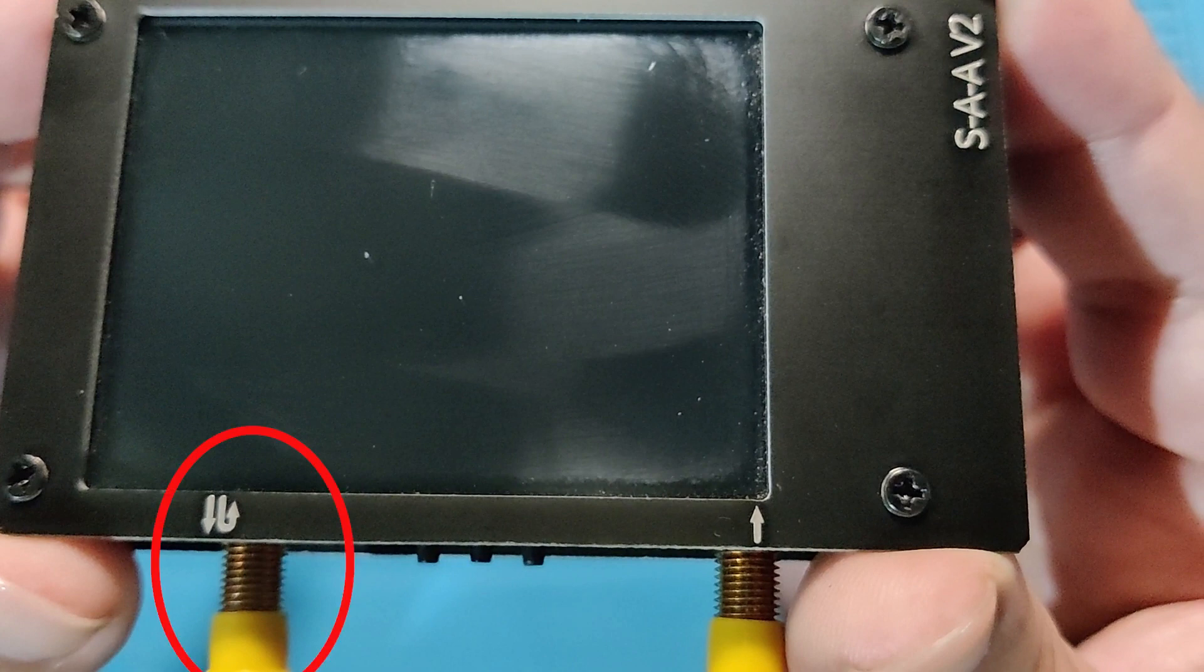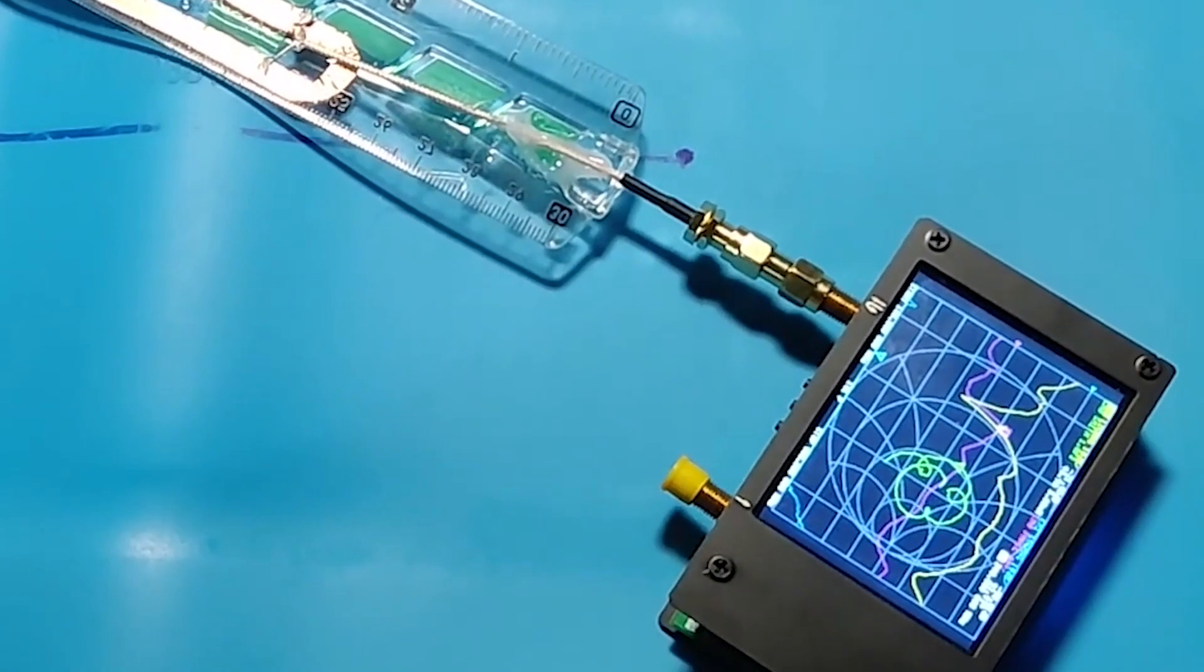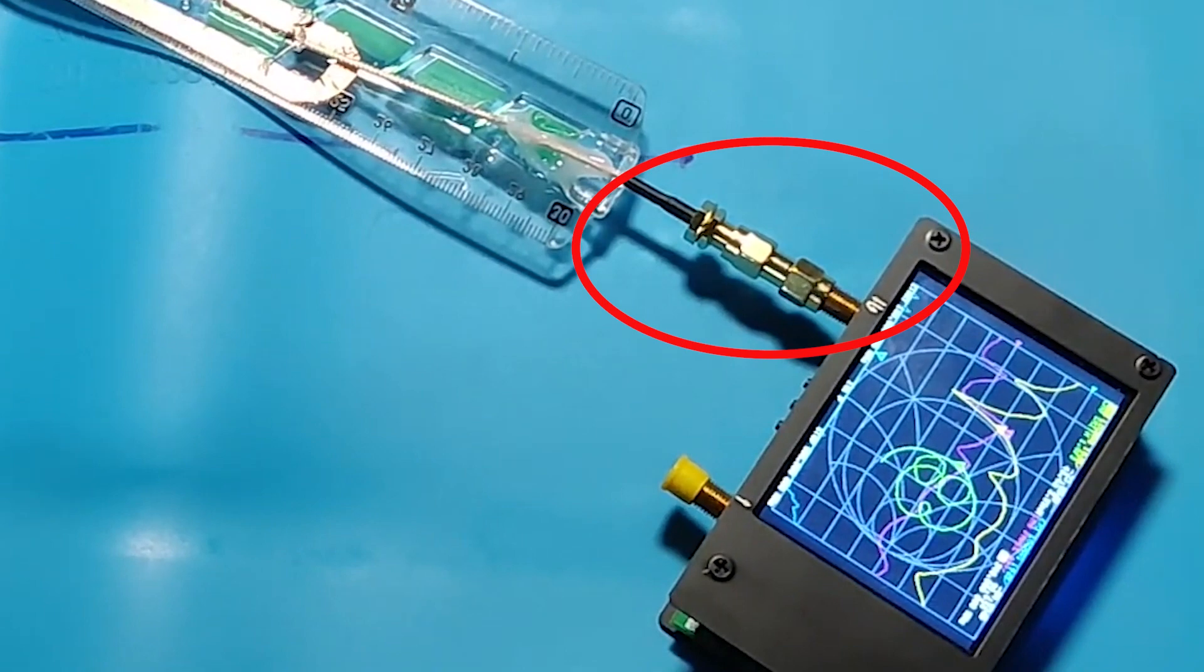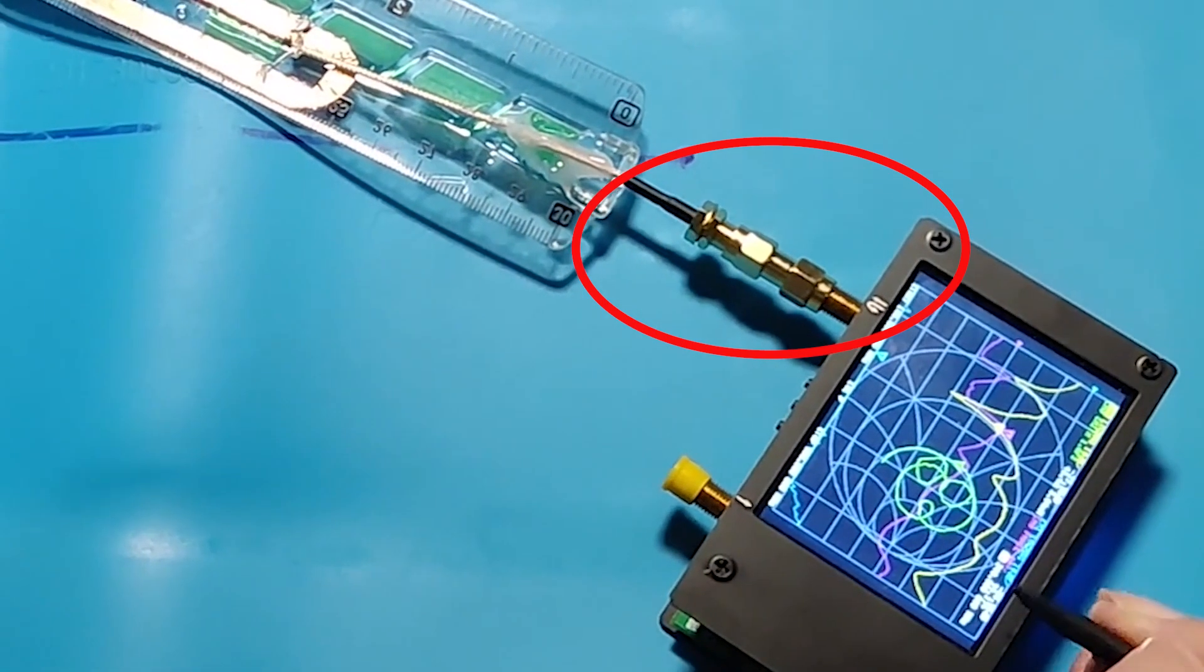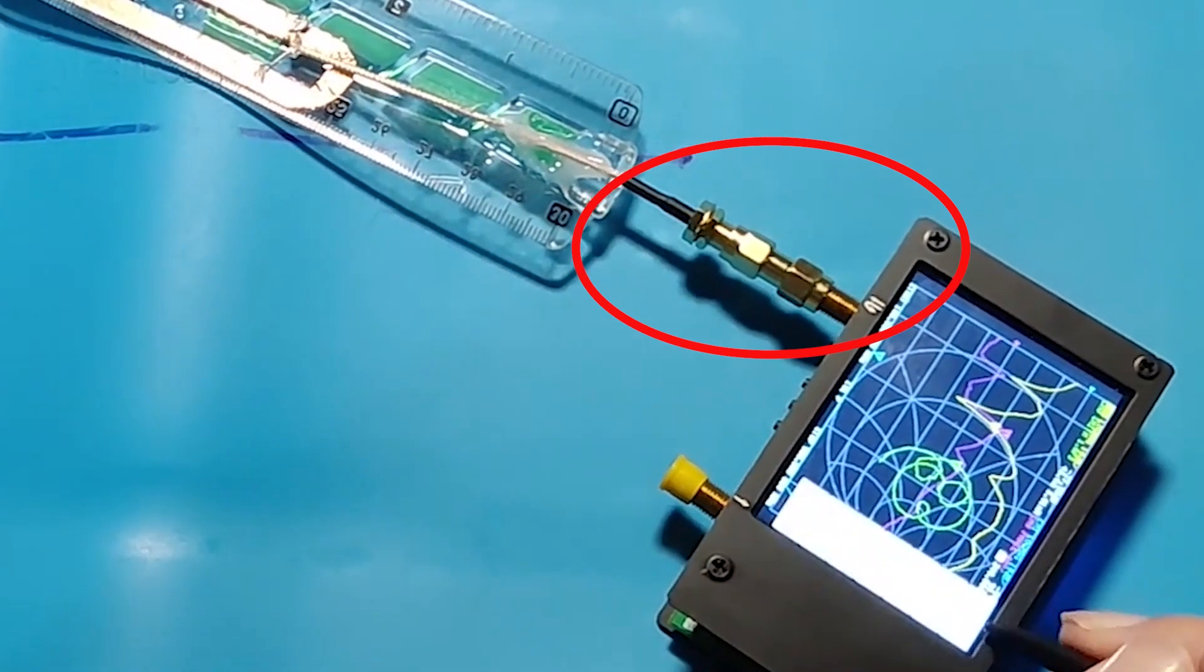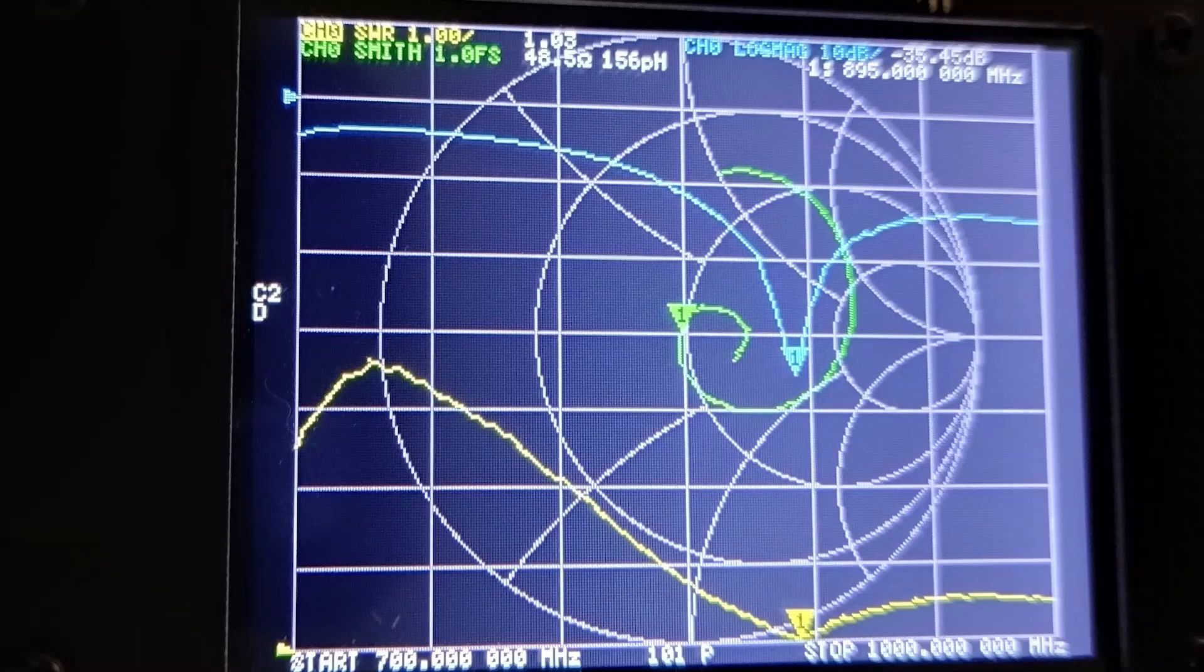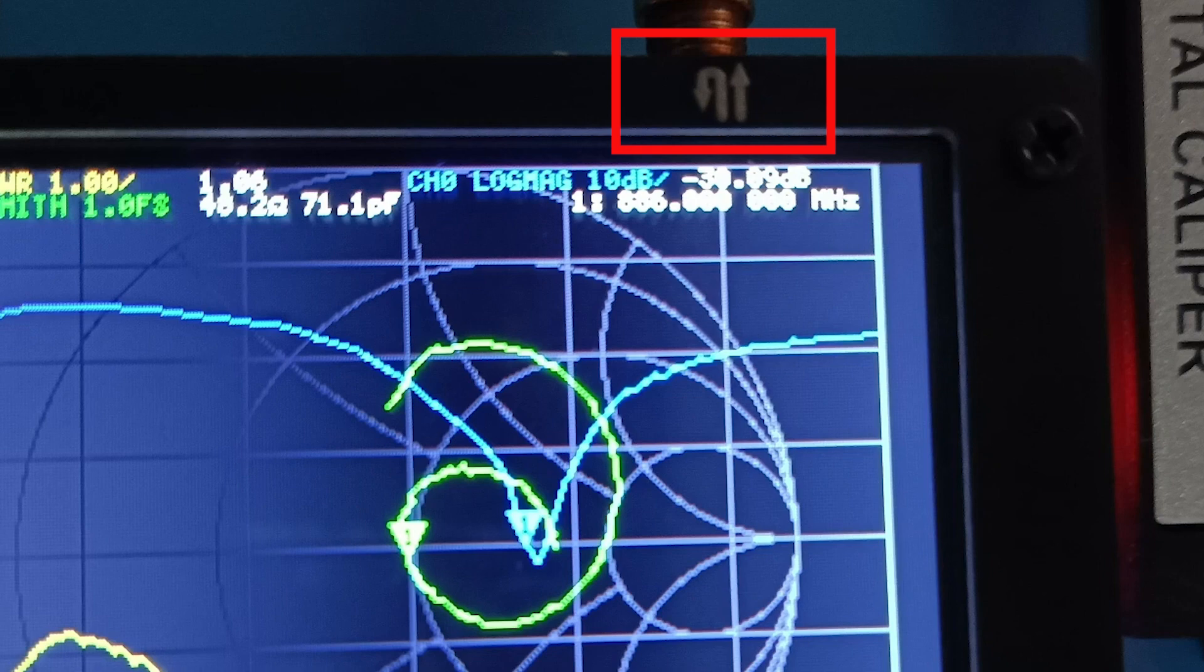The S11 port can be identified very easily. It is marked with an arrow pointing outwards and a U-turn arrow. The S11 port provides signal to the attached device, cable, etc., and it also measures the reflections or reflected power. The straight arrow pointing outward represents the outgoing signal, while the U-turn arrow represents the reflected signal which goes into the VNA.